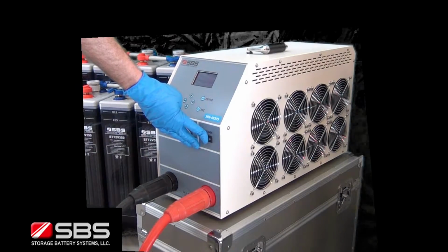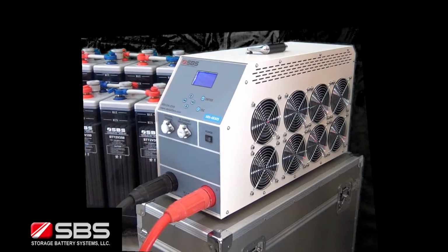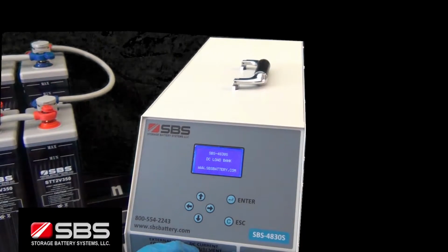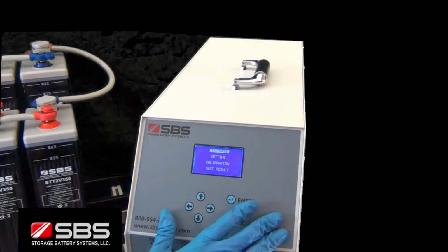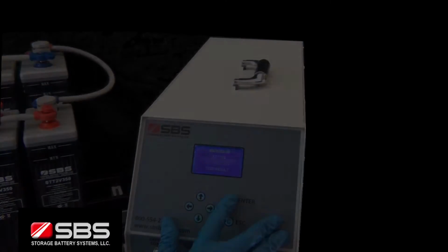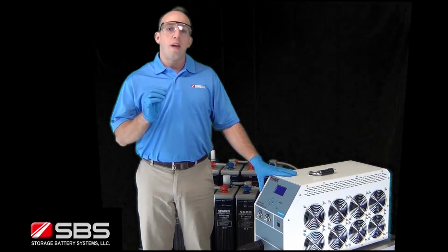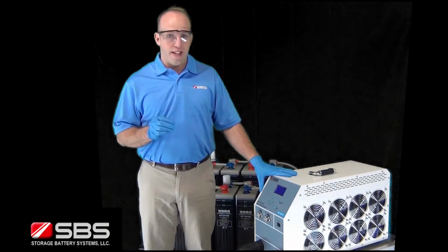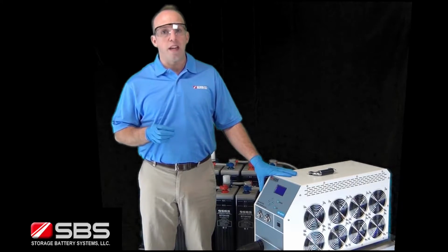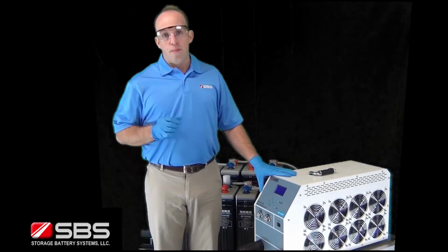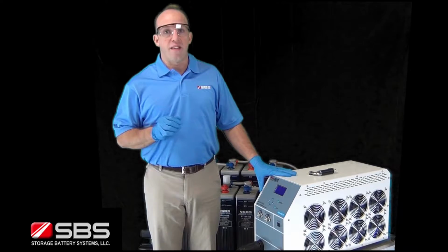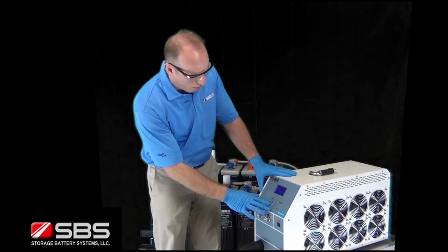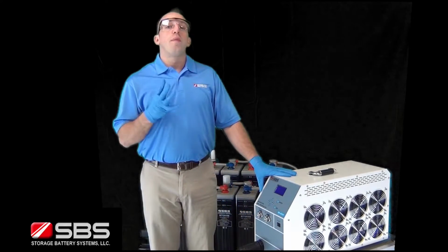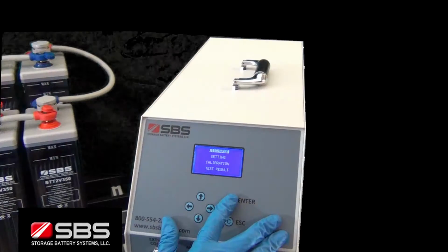Turn the power switch to on to start up the SBS S-Series load bank. On the LCD screen, you will see our company name, the model number, and the tester name. Press any key to enter the main menu. Before you run any tests, you will have to determine the parameters of your battery test to correctly program the load bank unit. To set the appropriate parameters, enter the settings field by using the arrow buttons on the control panel. There are 4 parameters that need to be set before testing.